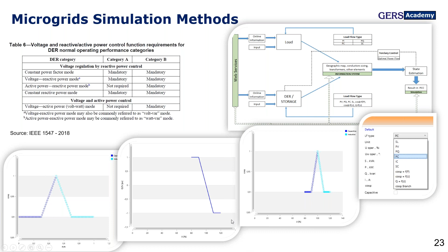It's been noted that we have conventional control modes in conventional power systems, and IEEE 1547 specifies additional modes that should be able to be set on the DER. Some operation modes are for keeping the voltage, some are for keeping the reactive power, and we can see how, according to the active power being generated, we can have control on the power factor, or control according to the voltage profile.